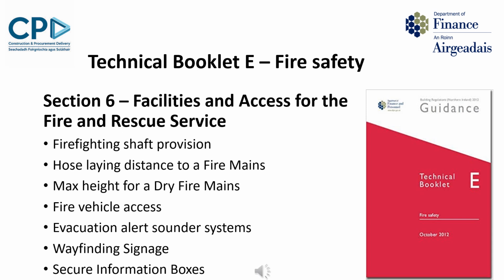In section 6 of TBE, Facilities and Access for the Fire and Rescue Service, there are a number of changes to assist the Fire and Rescue Service in operational functions of firefighting and search and rescue. So these are changes to firefighting shaft provision, hose laying distances to a fire main, a lower maximum story height for provision of dry fire mains, more onerous fire vehicle access distances, and new requirements for the provision of evacuation alert sounder systems, wayfinding signage, and secure information boxes in buildings containing flats with a story more than 11 metres above ground level.